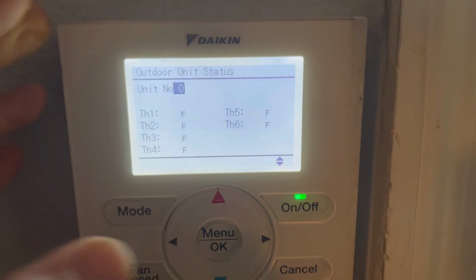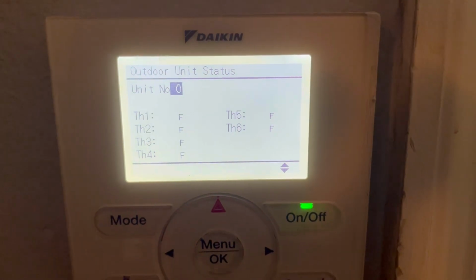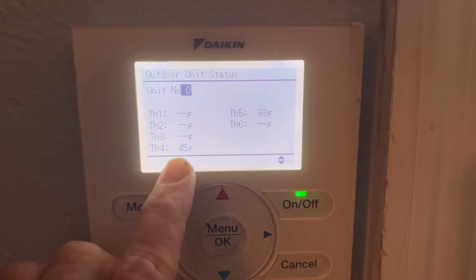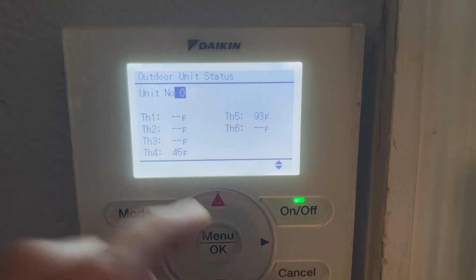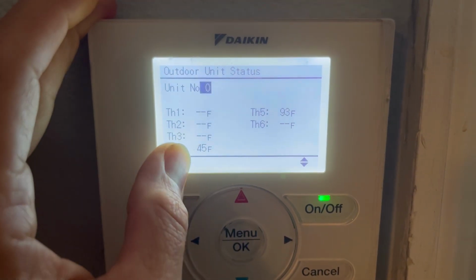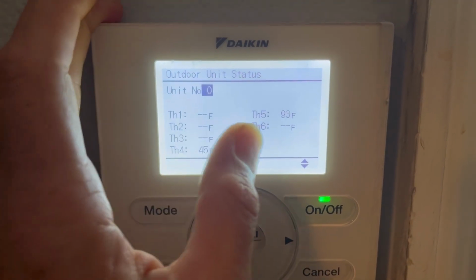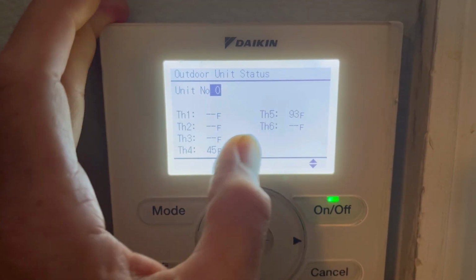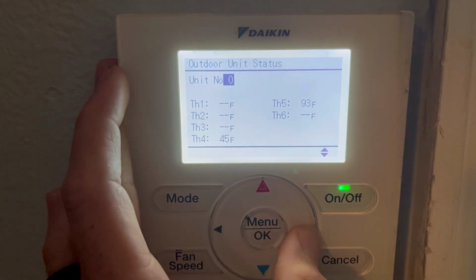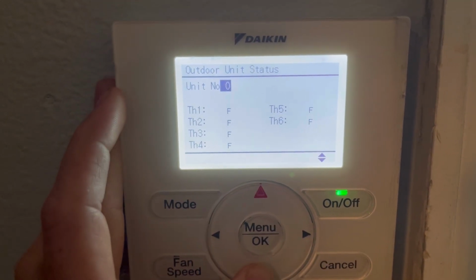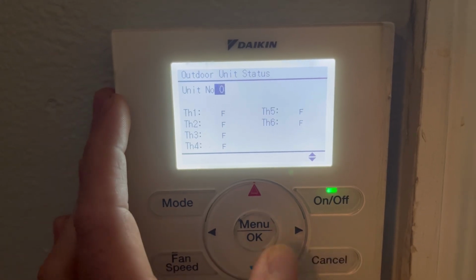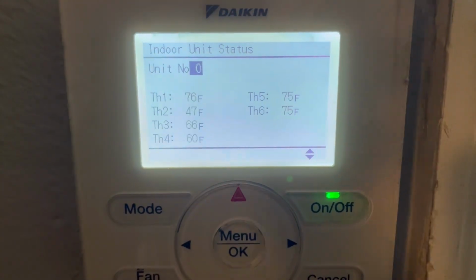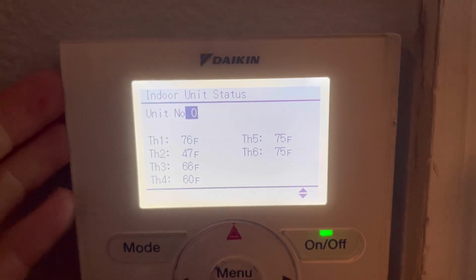Outdoor unit status. Now this is going to depend upon the type of unit that you have hooked up and what series it is. I have 45 degrees and I have 93 degrees. And typically these refer to the saturation temperature for my evaporator, and then the 93 is usually my TCs, TE and TC. Now this changes based upon the unit that you have. If you have multiple units, you can cycle through the sensors. And then the other one, this is the second most important, well, probably maybe the most important. This is your indoor unit status.